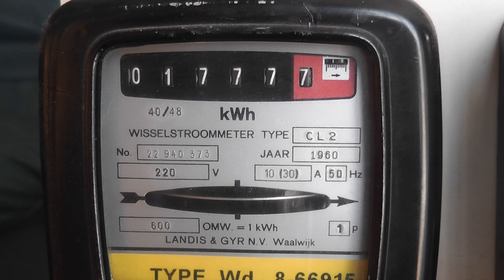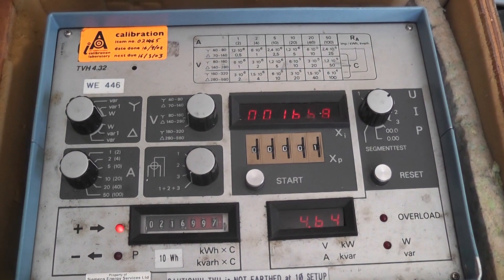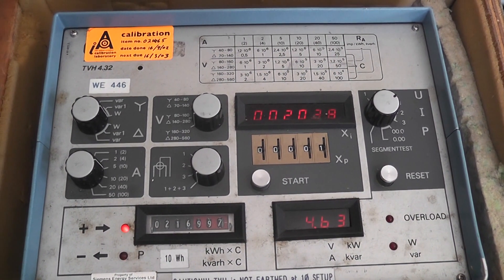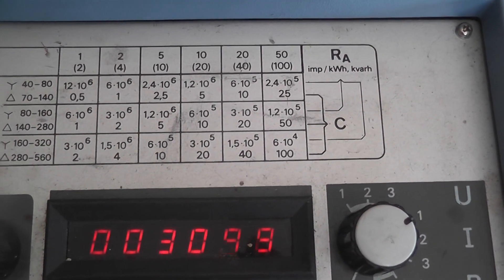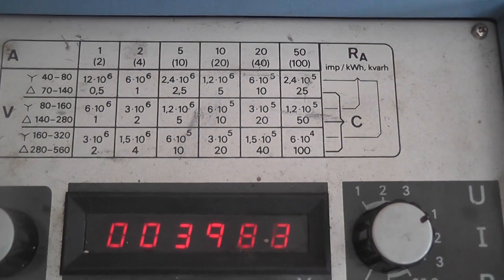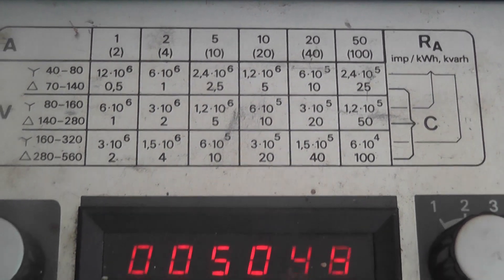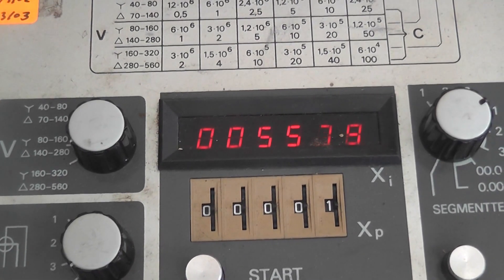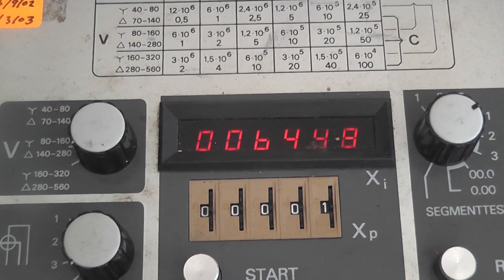The meter constant is 600 revs per kilowatt hour. The standard I'm using is Landis & Gyr TVH4-32, and I'm in the 5-10 ampere range on this column here. 600,000 impulses for 1 kilowatt hour. So when the meter clocks up 10 revolutions I should get a number of 10,000; 20 revs, 20,000, and so on.